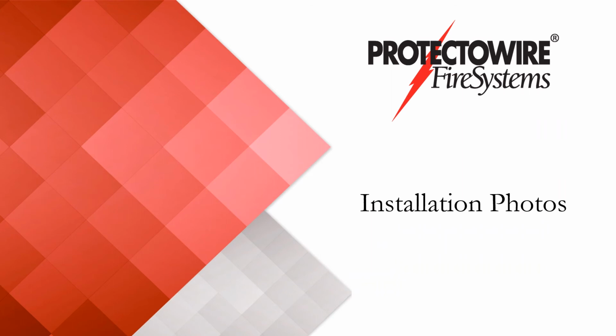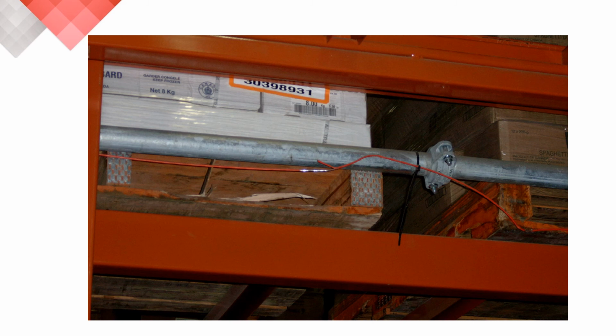Now, let's quickly review some installation photos to apply what we have just learned and discussed. In this slide, you can see the Protectowire is strapped directly to the in-rack sprinkler piping. While it appears as though the installation has used our double loop pipe straps, that's about the only thing that is correct in this photo. As mentioned earlier, Protectowire does not recommend putting our linear heat detector on the in-rack sprinkler piping.